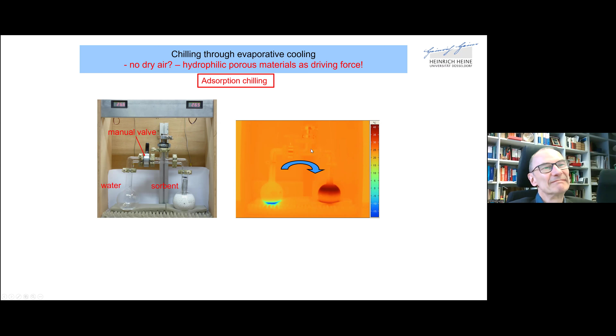This is initially a one-time process. To make it technologically interesting, one has to turn it around. Let's look at this working cycle again, where water or another working fluid is drawn to evaporation by an active, empty sorption material. Heat of evaporation is drawn from the environment, generating cold, and heat of adsorption has to be dissipated to the environment. This unit, an alternative air conditioner, has to be regenerated by applying heat of desorption to the sorption material, releasing the water again, which has to be condensed to give the working fluid and re-enter the working cycle.